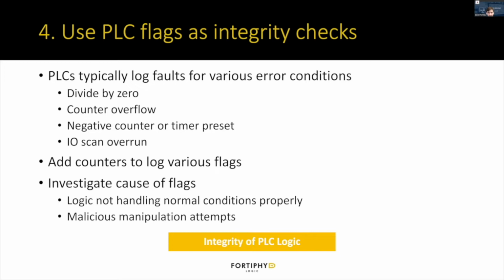The next practice is using PLC flags as integrity checks. Most PLCs, including CODESYS, have different log faults and flags for various error conditions. For example, divide by 0, like a math error, counter overflow, negative counter timer presets, or some overrun flags and issues. So this practice is all about adding counters, making sure you're tracking all those flags and errors, and making it so you can investigate them later. So not just ignoring them, not just handling them and assuming that everything's okay. Making sure you actually log that so you can investigate it later to verify whether maybe you need to update your code to handle some weird condition better, or maybe it's some kind of malicious manipulation happening that you need to investigate and address.